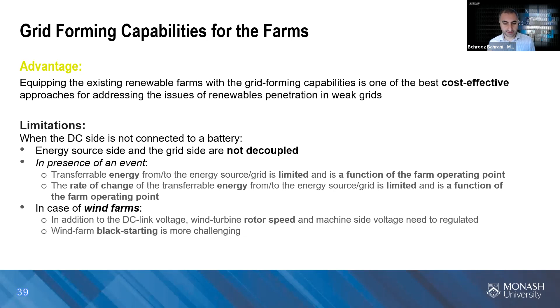There is one example you can read more about in the paper I've put at the bottom of this slide. Siemens Gamesa in Scotland operated a Type 4 wind turbine, including 23 full converters, 69 megawatts, for six weeks back in 2019 in VSM mode, virtual synchronous machine mode. They tested many different scenarios, and you can find the details in different literature around this particular farm, which is a very good example showing that it's possible to apply grid forming capability to wind farms.